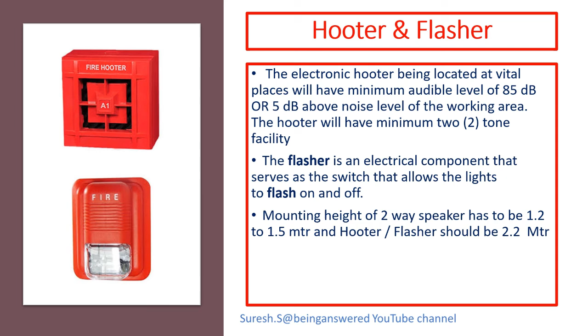Hooter and flasher. The electronic hooter, being located at vital places, will have a minimum audible level of 85 decibel or 5 decibel above the noise level of the working area. The hooter will have minimum 2-tone facility. Flasher is an electronic component that serves as a switch that allows the lights to flash on and off. Flasher is used in the building to facilitate differently abled people who are not able to hear the sound. They can recognize the light flashing on and off and escape from the building quickly without waiting further in the fire circumstances. Mounting height of two-way speaker has to be 1.2 meter from the FFL level to 1.5 meter from FFL level, and hooter flasher should be at 2.2 meter from FFL level.